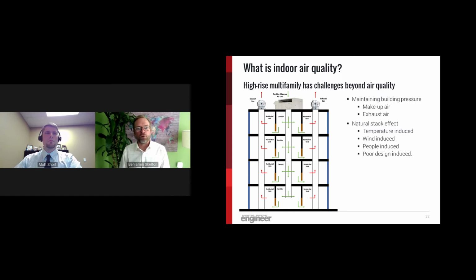When you look at multifamily high-rise buildings, these buildings have more challenges than just air quality when it comes to ventilation. Building pressurization is typically one of the biggest challenges when you come into high-rise and tall building design. Not just office buildings, but multifamily high-rise buildings have more challenges because they generally have operable windows. And now, instead of an automation system that's controlling the dampers and bringing the ventilation in automatically based on sensor data, you have a person that has the ability to change the whole dynamics of the building just by opening a window. And so when we look at these buildings, it's trying to balance makeup air, it's trying to balance exhaust, but it's also trying to manage the natural stack effect of the building.